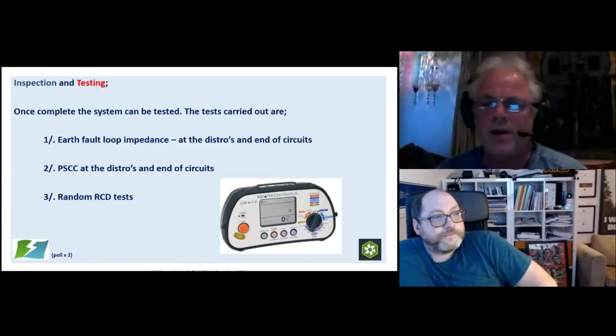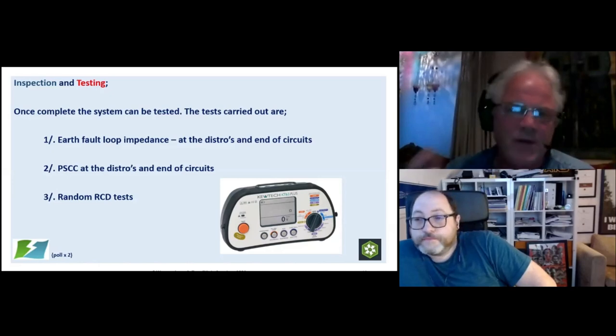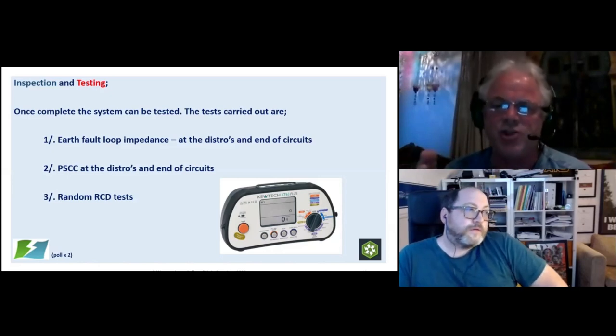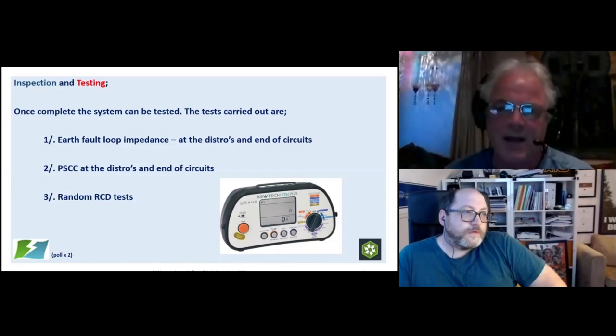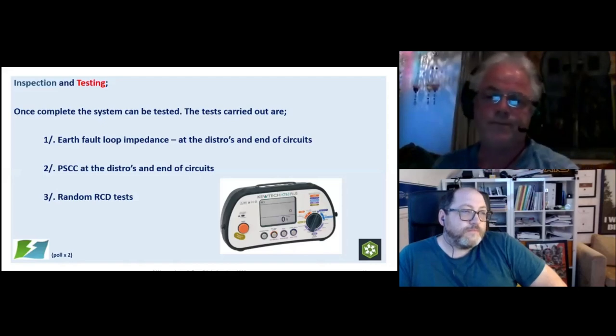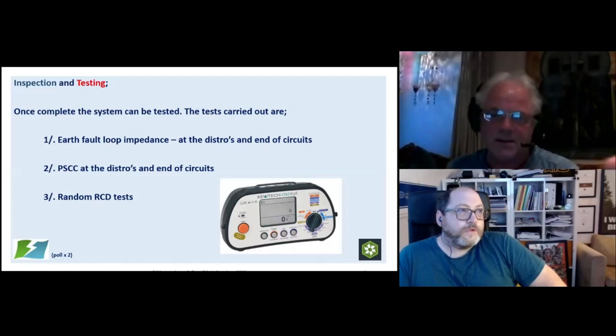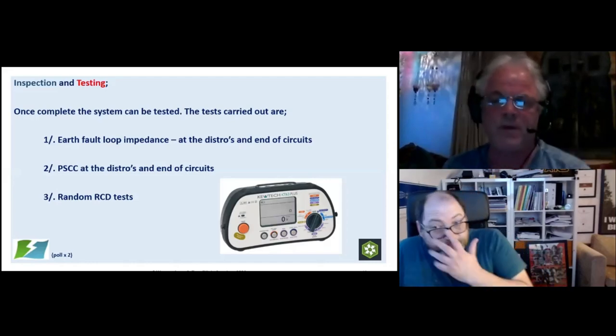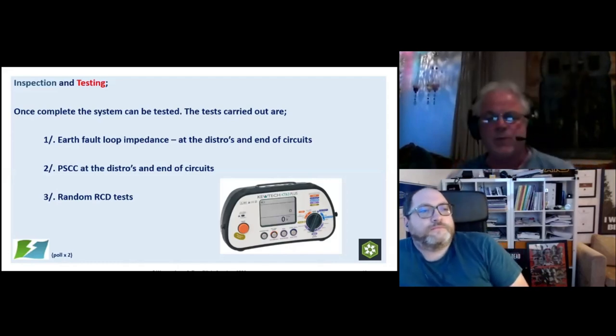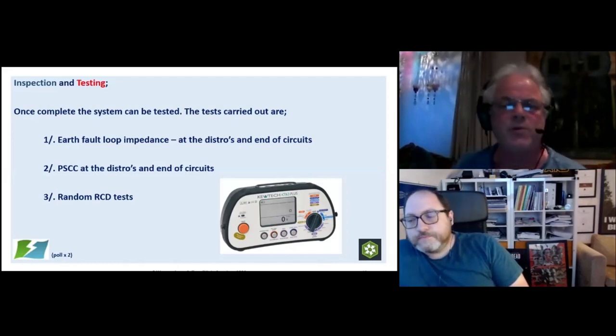Remember that when we're looking at protection of electrical systems, with so much emphasis on fault protection against electric shock, what we've got to really consider is the other big issue, which is fire protection. Yeah, and if we don't get proper disconnection of the circuit under short circuit conditions, then the next thing that will happen is the cables are going to overheat and we could possibly have a fire. And far more people die from fires than die from electric shock. So it is an issue, and as you said earlier, this is something that we've picked up from doing temporary systems.